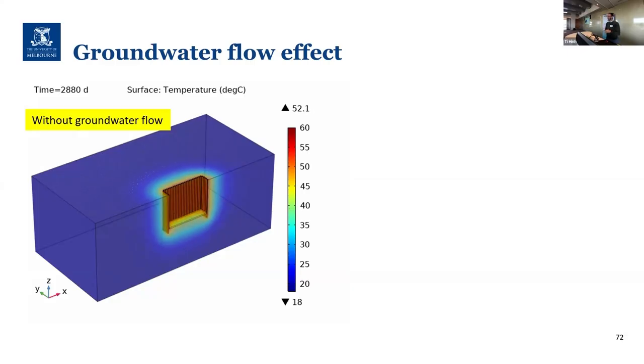If you have an unbalanced thermal load, like here where the State Library and Parkville Station require a lot of cooling and air conditioning, that means you're rejecting heat to the ground all the time, and eventually you may overheat the ground. That's true in the absence of groundwater flow.